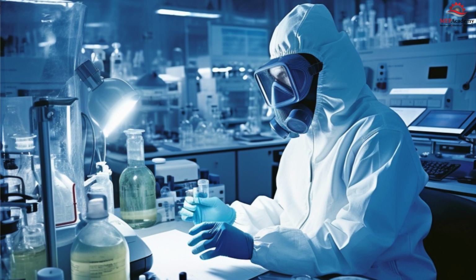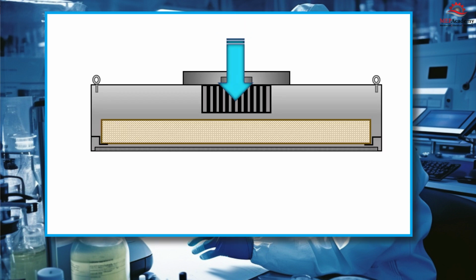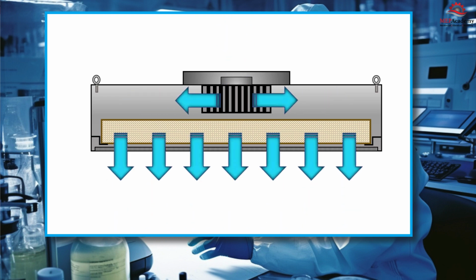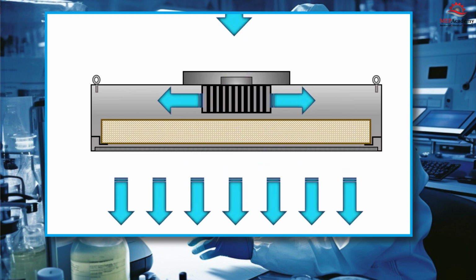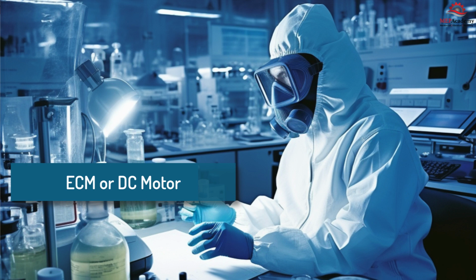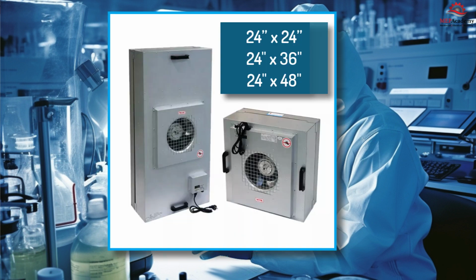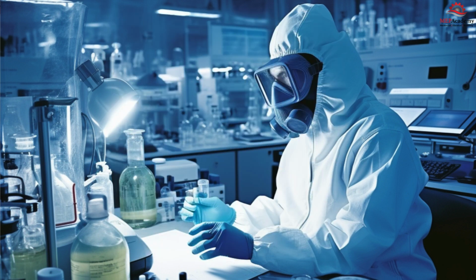Here's how an FFU typically works. Fan. The FFU contains a fan that draws air into the unit using various system configurations. The fan is using an electronically commutated EC or direct current DC motor that operates quietly and efficiently. The most common sizes are 24-inch by 24-inch, 24-inch by 36-inch, and 24 by 48-inch fan filter units.